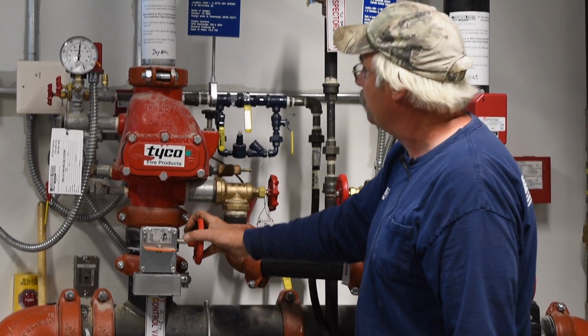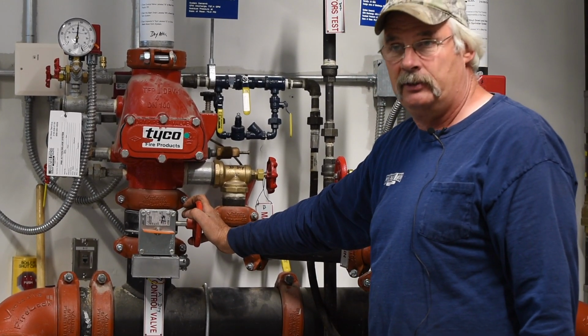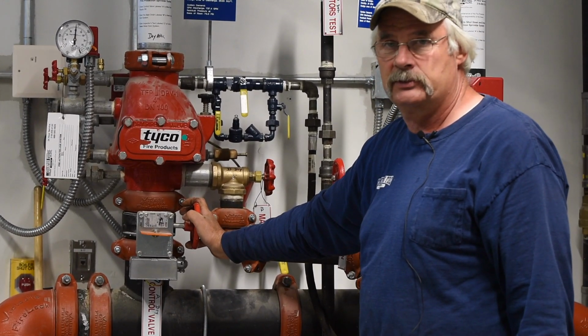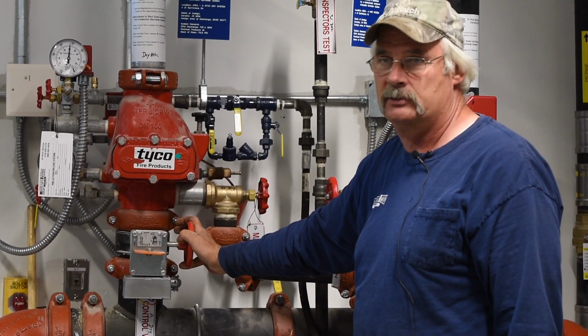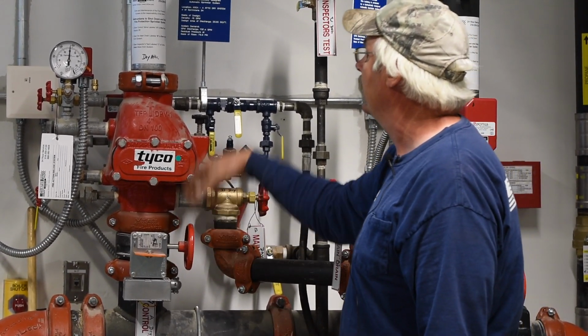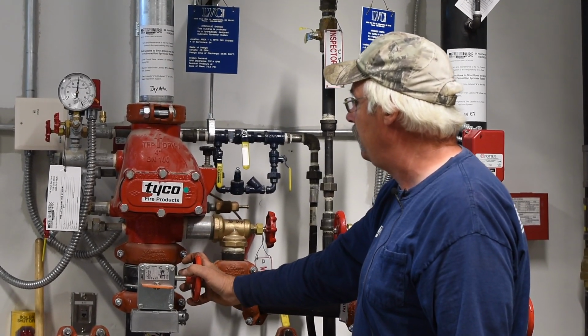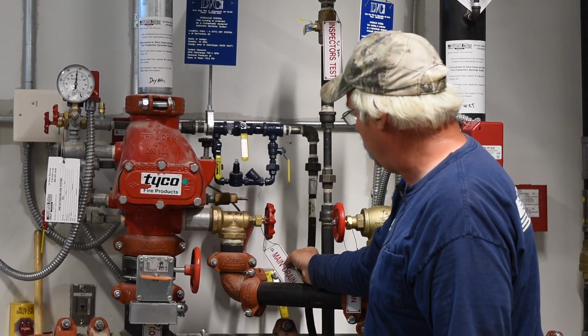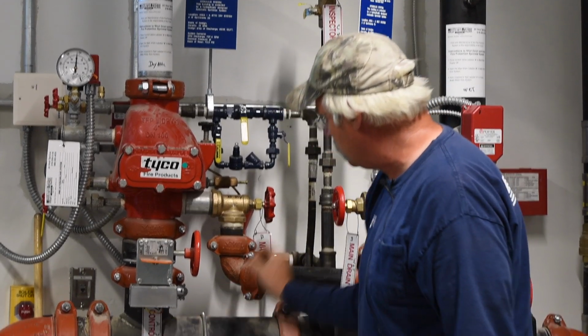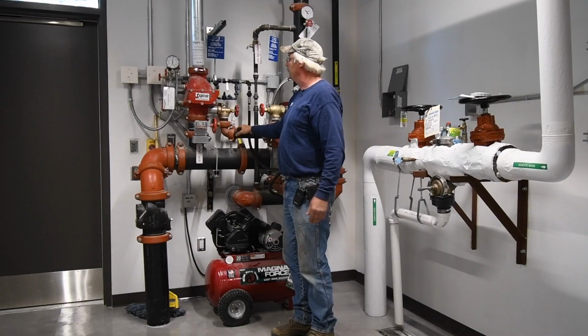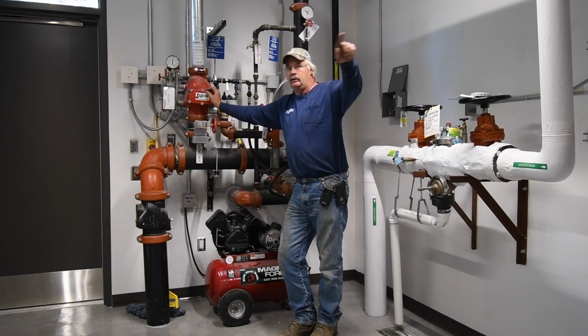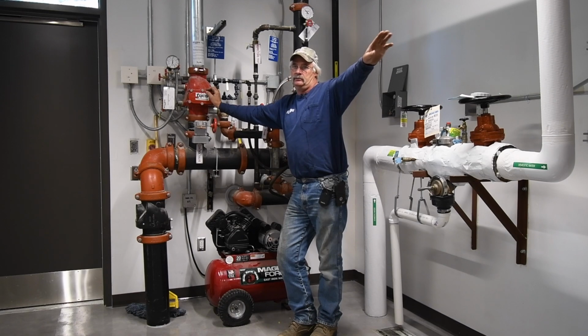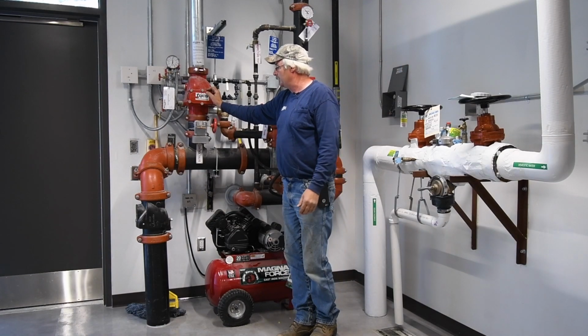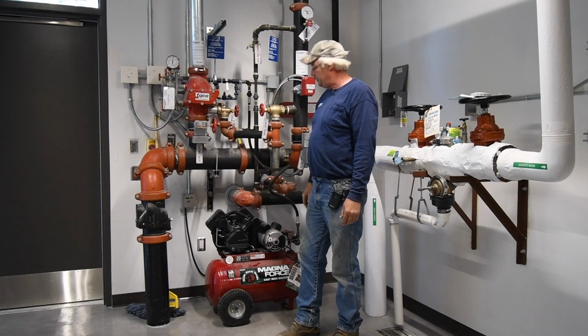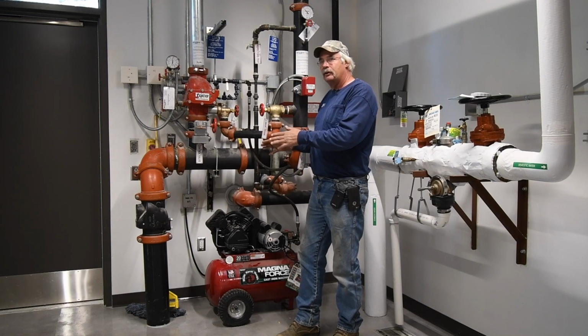Again, we have 3 steps to shut a system down after a fire, or say you had vandalism or one of the kids broke a head off or something. Step 1, close control valve A. Step 2, open main drain B. You'll notice that everything says dry, main drain B. The inspector's test is straight down the corridor above the ceiling in the classroom, just to the south of us, on the east side here. So that pretty much covers all of the wet, covers the dry.